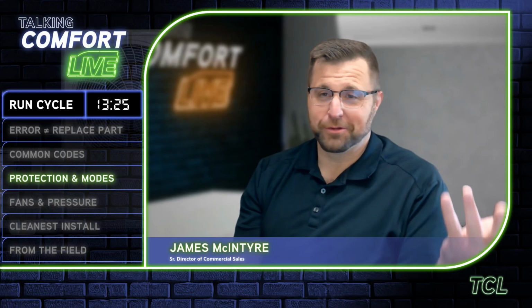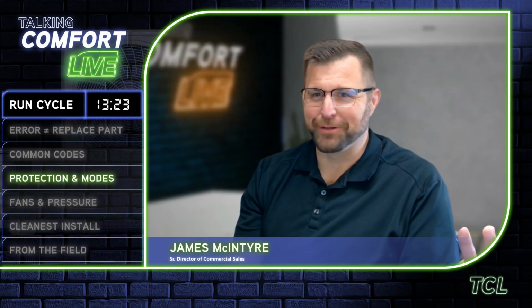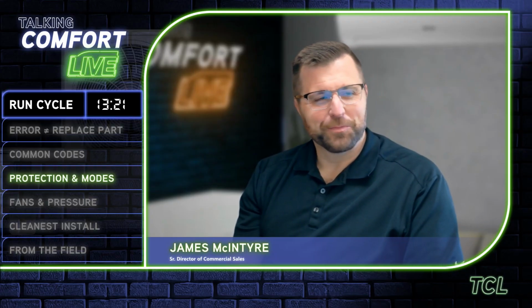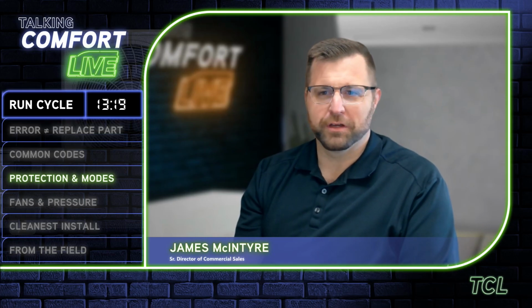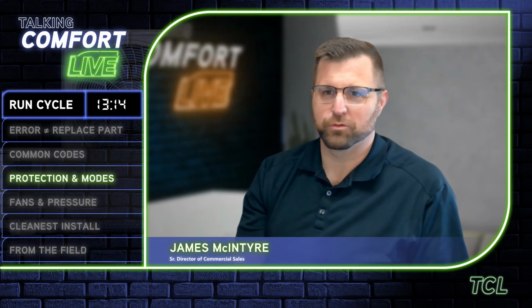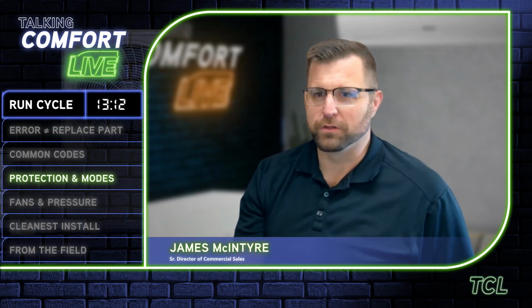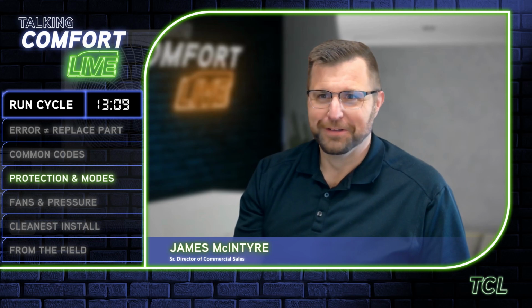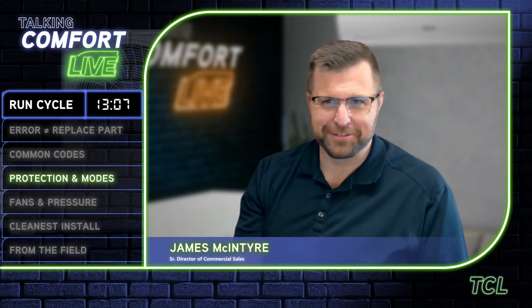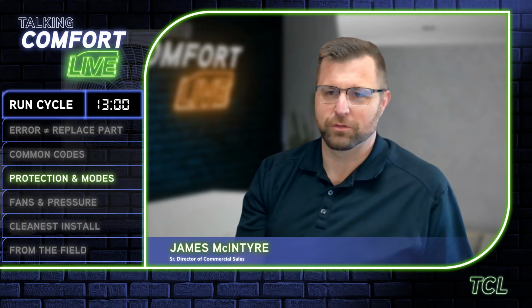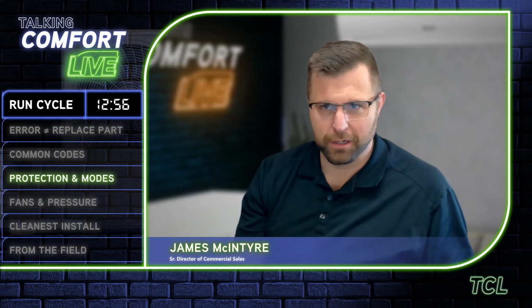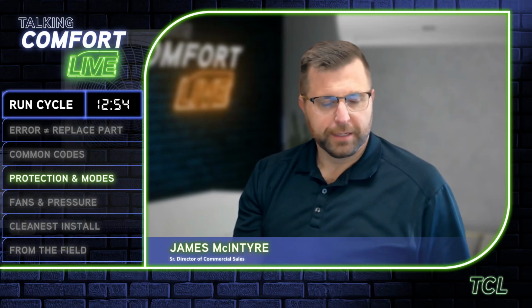But yeah, it depends on your time delay on the thermostat, how long it takes to trip again, right? But think back, high pressure protection on anything that you've ever worked on. If you've seen high pressure protection before, hey, that pressure switch was tripped out, it must be a bad pressure switch. Well, how long did it take you to learn that you switched out a pressure switch and it still didn't fix it? So think back, what were the conditions that made it trip the last time you saw it? Regardless of what you're working on, there's a commonality all the way through. Still an air conditioner, right.